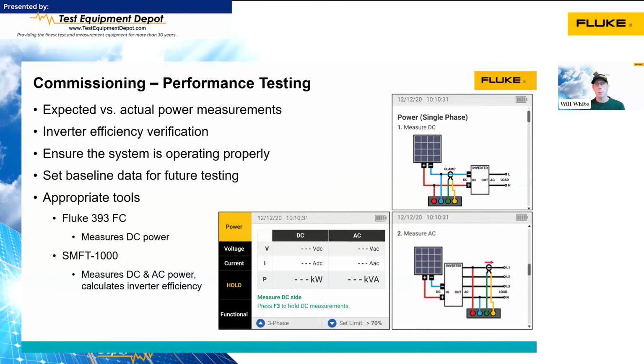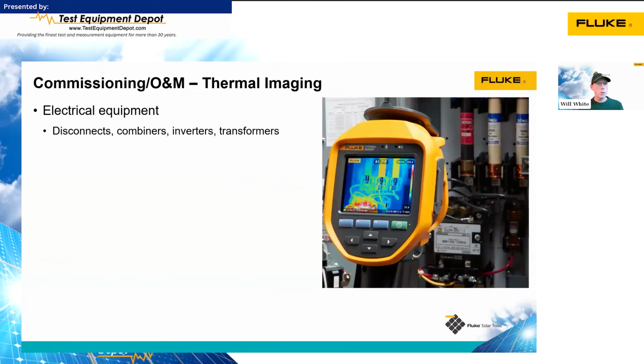So if you have something like a microinverter where you don't have access to the output conductors of that inverter, it's going to be hard to measure that inverter efficiency in that case. Another thing we do in commissioning and in operations and maintenance is thermal imaging. So we can use our handheld thermography to look at all kinds of electrical equipment, from our disconnects, combiner boxes, inverters, transformers, essentially anything electrical. We can use it also on modules.